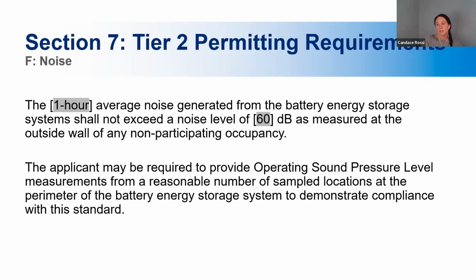Next is the requirement based on noise. This requires that a 1 hour average noise generated from the battery energy storage system shall not exceed a noise level of 60 dB as measured at the outside wall of any non-participating occupancy. I think a lawnmower operating is around 90 dB, and an air conditioner under 60 dB is considered quiet, so if it measures 60 dB outside your house you probably won't hear it inside, though these systems do tend not to be overtly loud. The applicant may be required to provide operating sound pressure level measurements from a reasonable number of sampled locations at the perimeter of the energy storage system to demonstrate compliance. The 1 hour and the 60 dB figures are both things the town itself can update depending on your community's character and what's best for your jurisdiction.